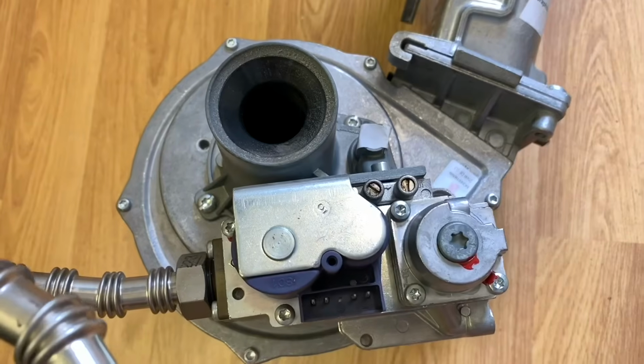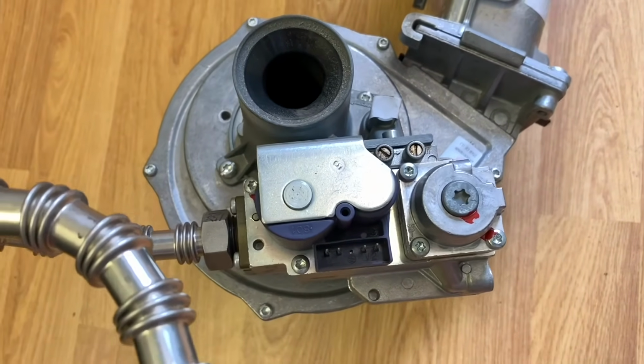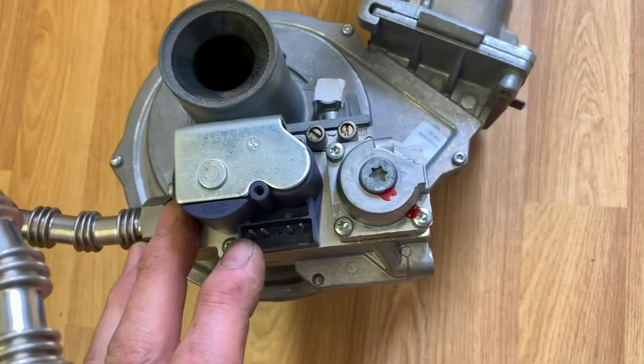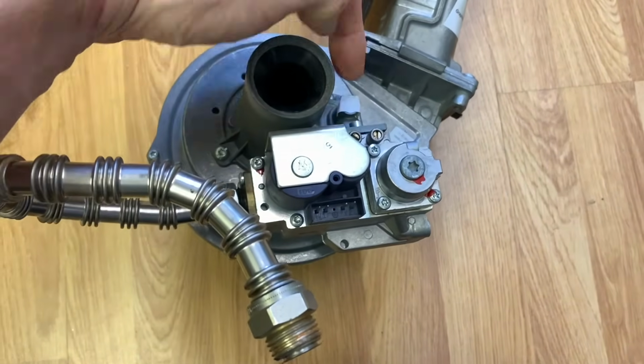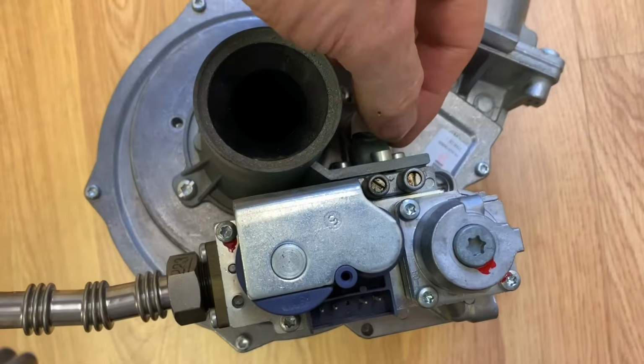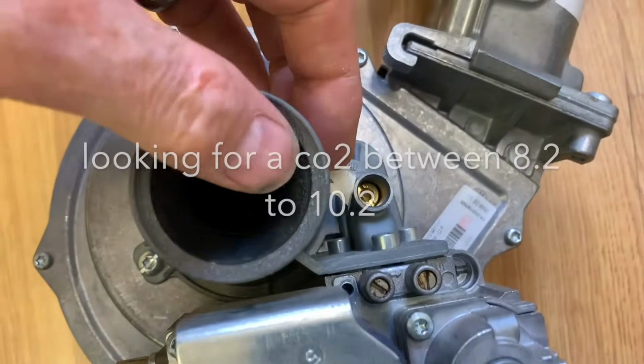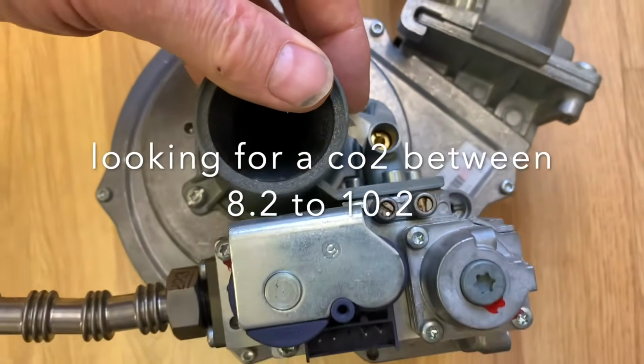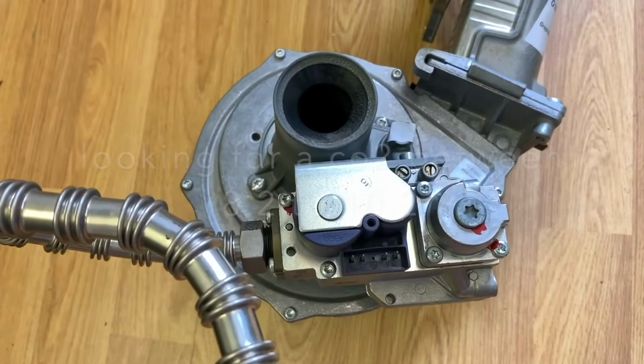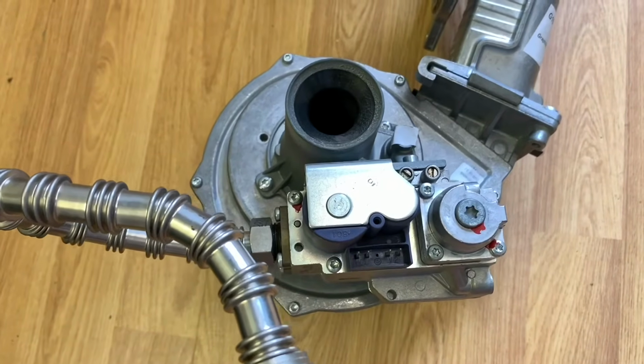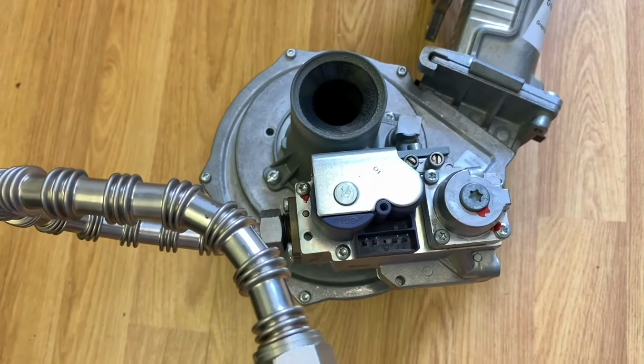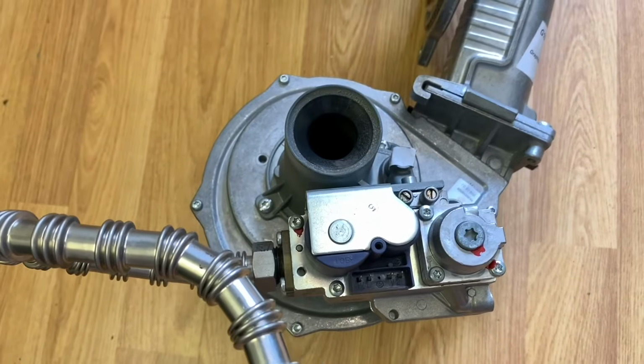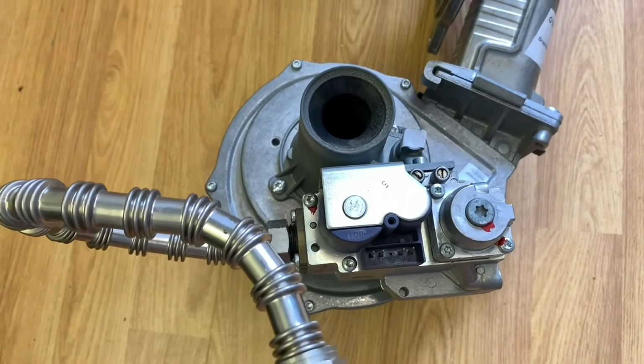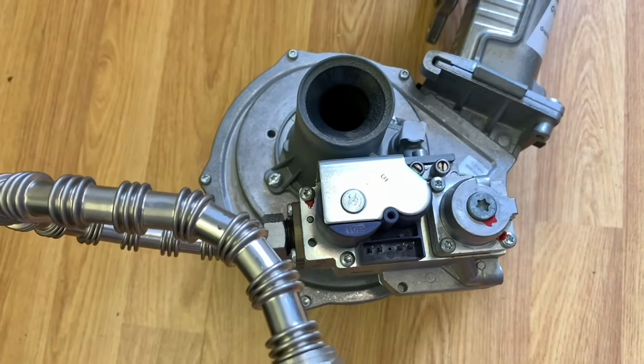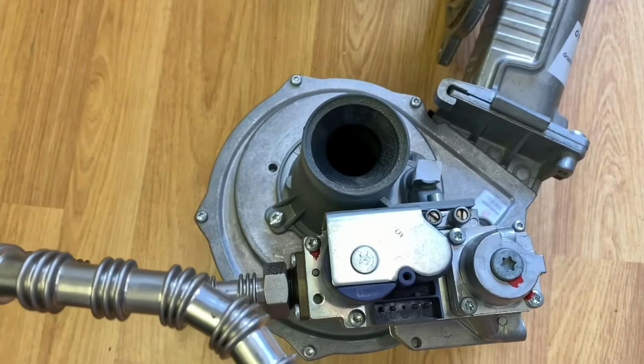The one at the top will give us a minus reading, which is no good to us because the manufacturers don't tell us what those readings should be. Now this is where we adjust the ratios. So behind this sticker is where we would use the Allen key to adjust our ratios using the flue gas analyzer. Now you should never really adjust the ratios on these burners unless you're changing it to LPG or your readings are out and you've done a full strip down service. You won't just rack up to this boiler, find out it's analysing incorrectly, and then start adjusting it without actually finding out why it's gone out.